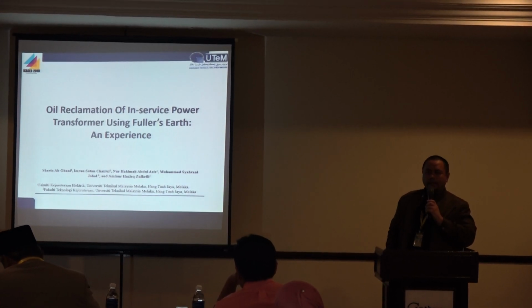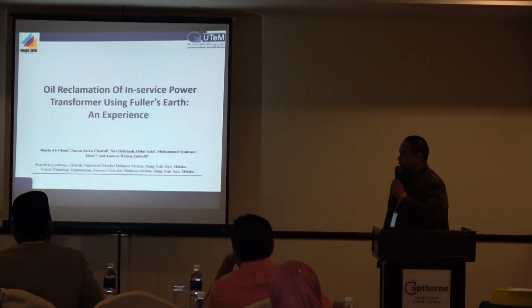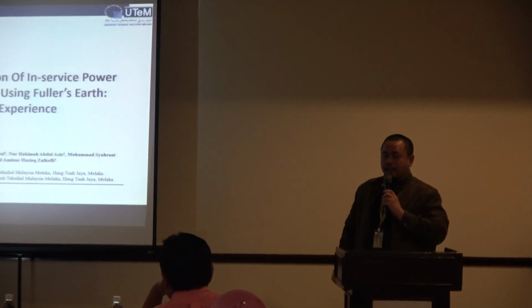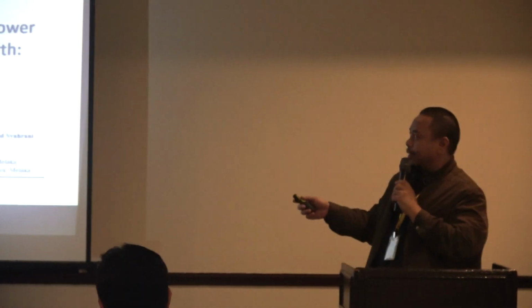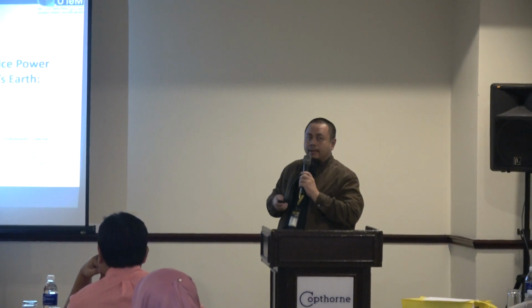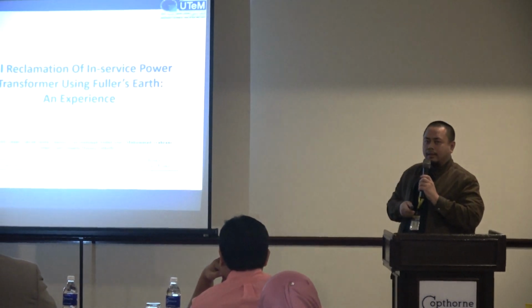I'm Shahrin Abdul Ghani from Universiti Teknikal Malaysia Melaka, and I just want to share our experience on using Fuller's earth as one of the absorbents that have been discussed. Like Nazlina said, they are using natural absorbents, but this time I'm using the commonly available commercial Fuller's earth absorbent. We are doing the reclamation of in-service power transformer oils by using Fuller's earth and sharing the experience on using it. It is some sort of review, but we did some experimentation on that.